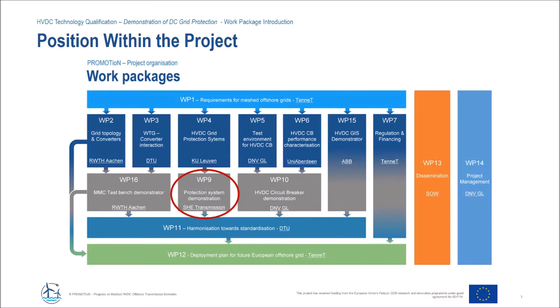So this will have been covered previously, but just to say that the challenge within DC grid is quite different to AC. The fault current has a very high rate of rise and a high steady state value, and of course there's no natural zero crossing either. Now there's a number of different protection strategies that can be used to overcome this. There's the selective, which is most like what we do on the AC network, where you could protect each individual line or segment. You could use a partially selective scheme where you split the network into different zones, or you can use a non-selective scheme where you would temporarily shut down the whole grid, isolate the fault and bring it back up again, but very quickly.